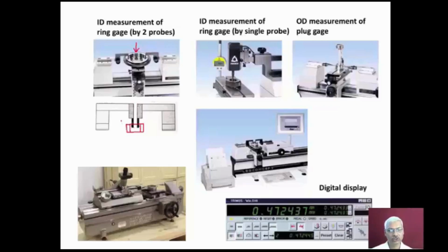Similarly, we can measure the outside diameter of the ring gauges, and here is ID measurement of a ring gauge using a single probe. And then we can see the digital display unit, and OD measurement of a plug gauge. Here you can see a digital display. When we move the probes, the amount of movement is displayed on the digital display. And finally, we can take out the inspection report using the printer.